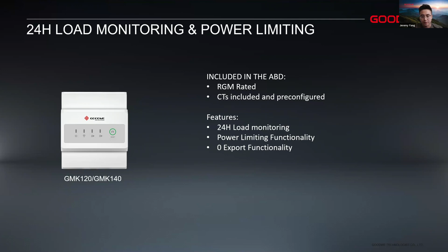And power limiting. As I mentioned before, the inverter can do derating. And when you do the derating, you will need someone to see the output power. So that's where the smart meter goes. When you have the smart meter and CTs, the power limiting can just be finished. And then also the zero export. As you may know, some utility companies won't allow you to export any power to the local grid. You can buy from the grid, but you cannot export. With this smart meter, you can achieve that function.